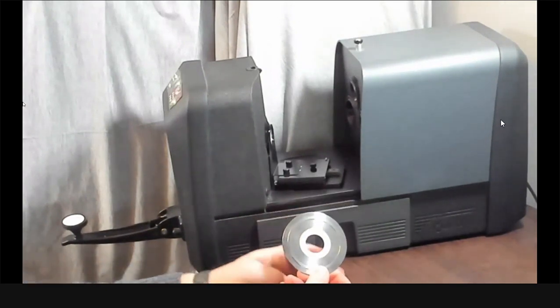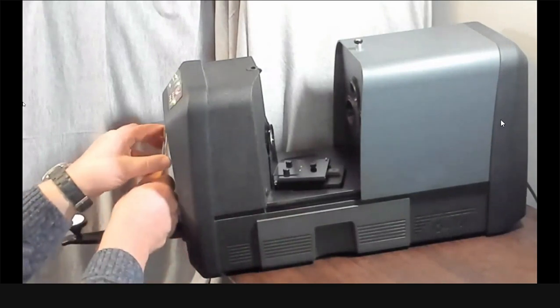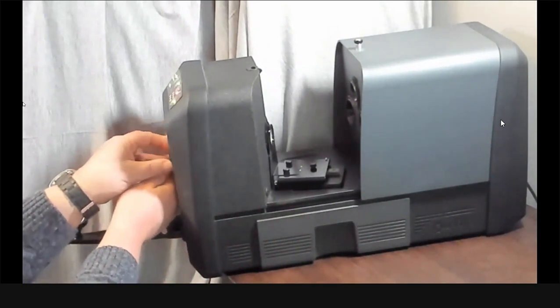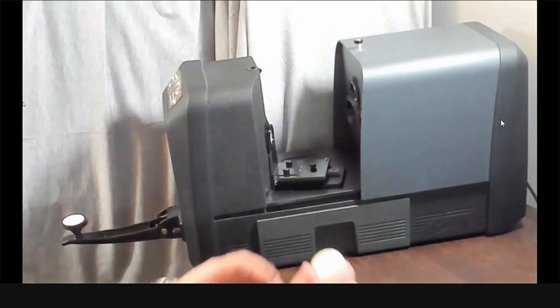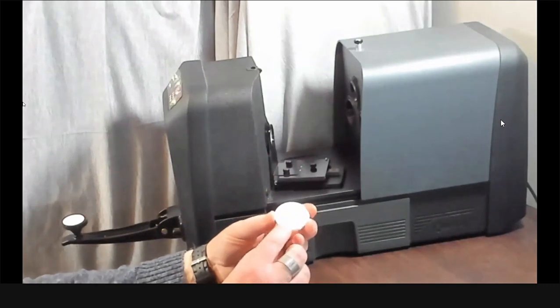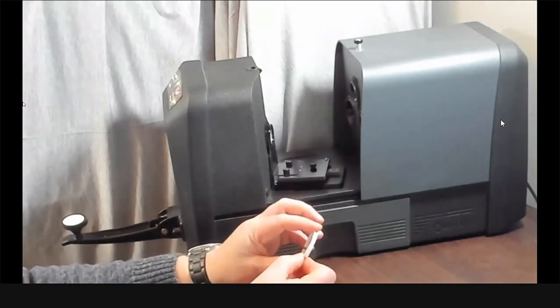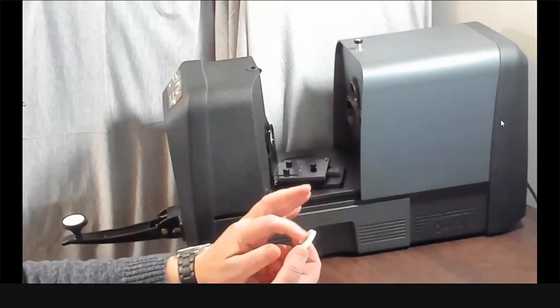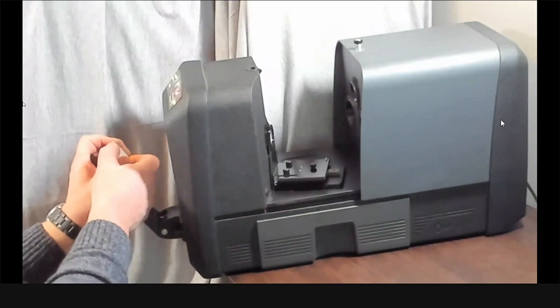This one is the normal one that does not have the white circle, and that one has the white. This one will complete the sphere, so you have to put that in. Make sure you have the correct aperture plate when you do the transmission measurement.